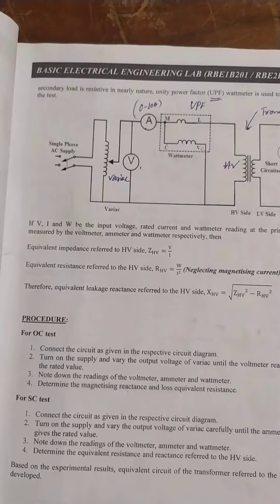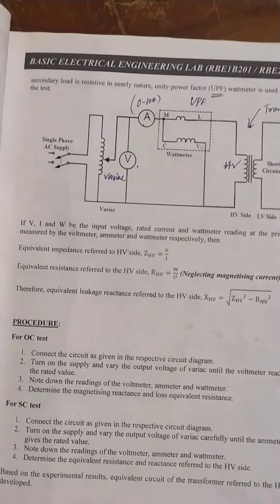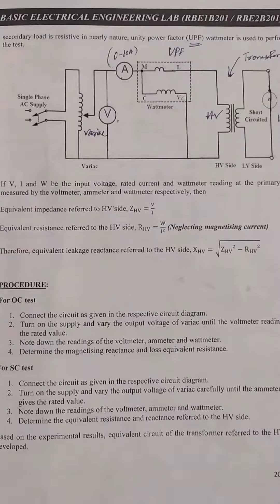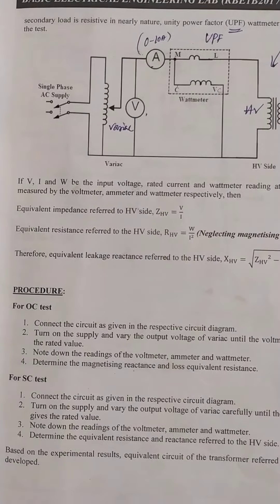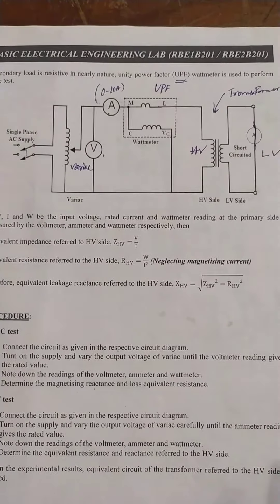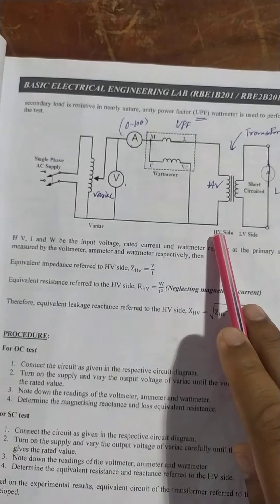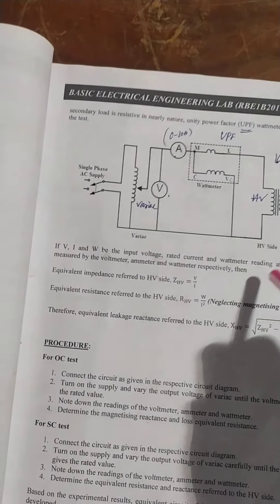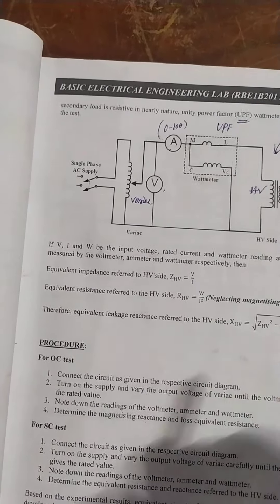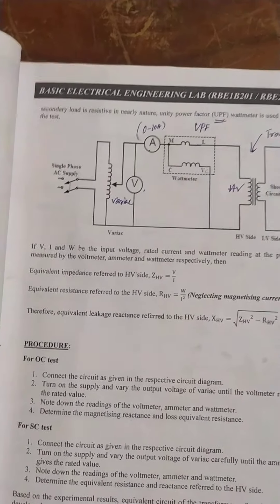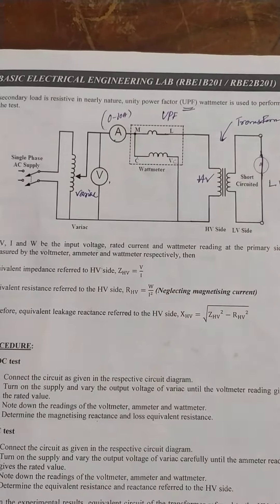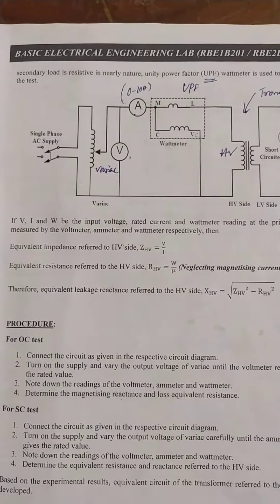To find the rated current: it is a 2 kVA transformer. kVA means 1000 volt-amperes, so 2 kVA equals 2000 VA. The rated current equals 2000 divided by 230, which is approximately 8.7 to 9 amperes. That is the rated current we will be working with.